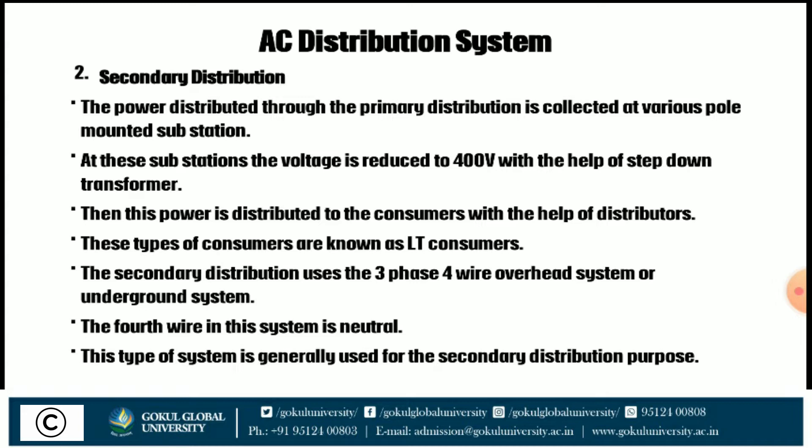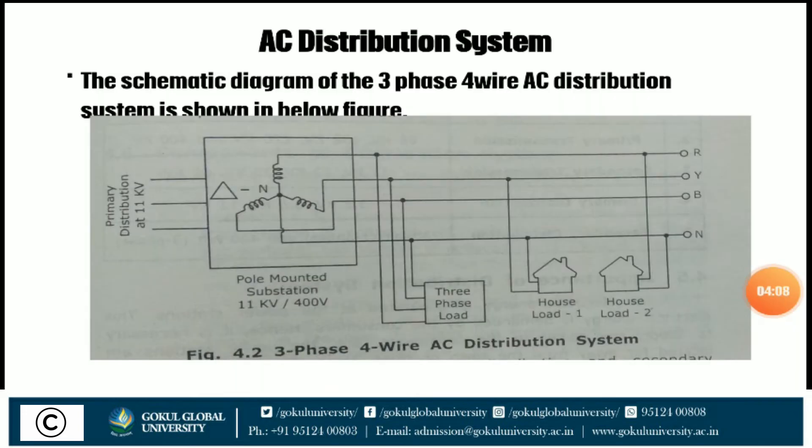The second part is the secondary distribution system. The power distributed through the primary distribution is collected at various pole-mounted substations. At these substations, the voltage is reduced to 400 V with the help of a step-down transformer. Then this power is distributed to the consumer with the help of distributors. This type of consumer is known as LT consumers. The secondary distribution uses a three-phase four-wire overhead or underground system. The fourth wire in this system is the neutral.